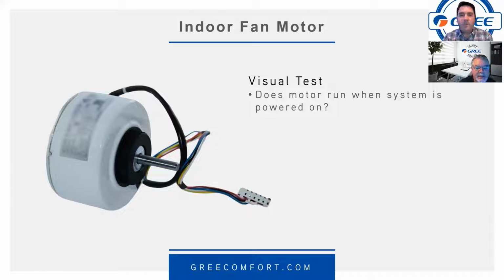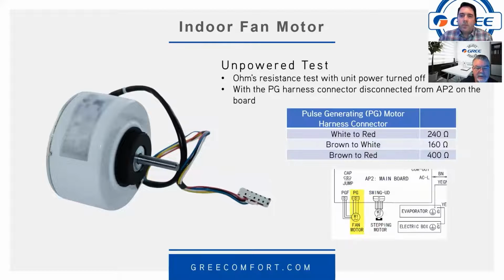So indoor fan motor. And again, that should be a pretty easy thing to visually test, see if the indoor fan is running. If the indoor fan was stopped, again, in heat mode, probably going to throw you an E1. But you're probably going to get a call from a customer a lot sooner than that because there's no air flowing in there. So that should be pretty easy to suss out. But so there's an unpowered test, ohms resistance test. Tells you from white to red should be 240 ohms and so on. Again, here's the board diagram showing you where that fan motor is located.